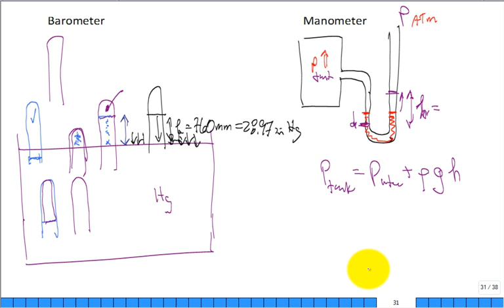How many people have seen a Bourdon tube pressure gauge? I used to bring one, I have one in my office. Basically the air or the fluid comes up and fills this C-shaped tube. Just like when you were little and blew into a party favor and it would unravel and blow out the end — well, if the pressure goes up, what does this C shape want to do? Straighten. And you hook it up to some mechanism to move and rotate a pointer, so the pointer changes location as the pressure goes up. That's a Bourdon tube, named after French engineer Bourdon.